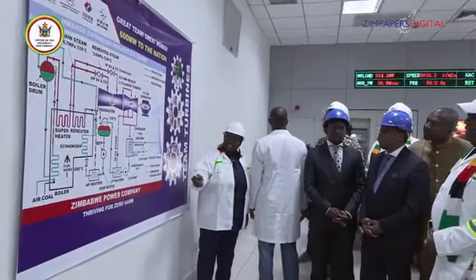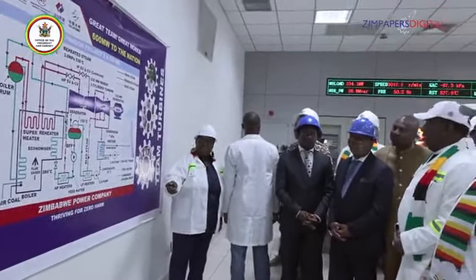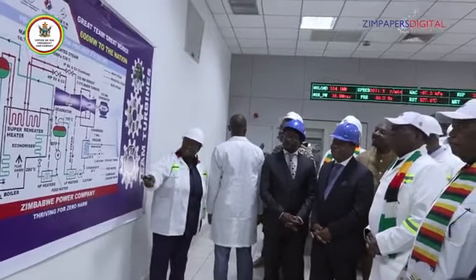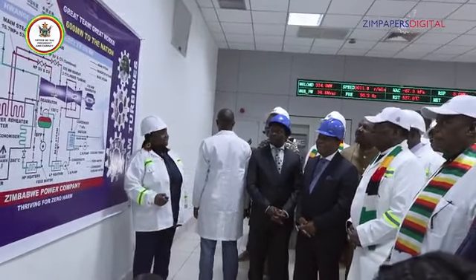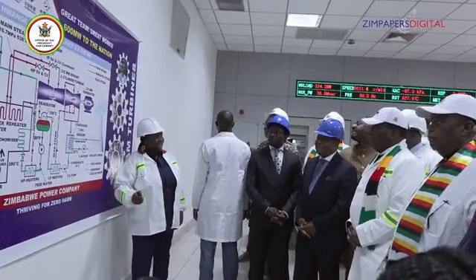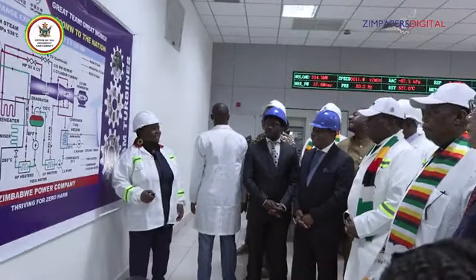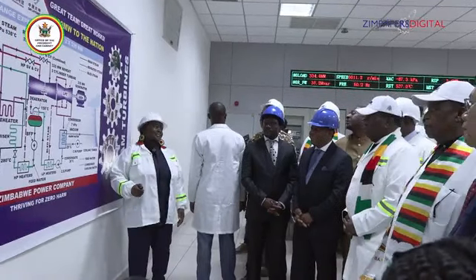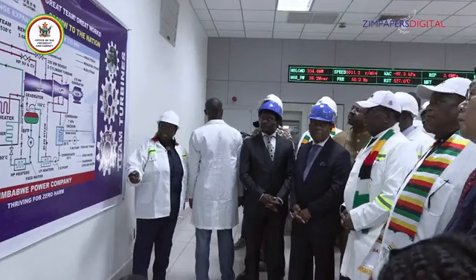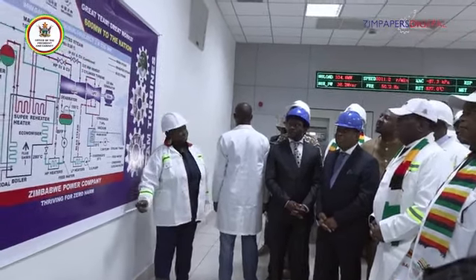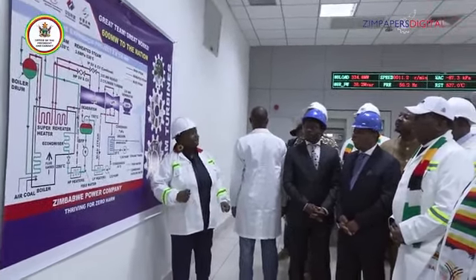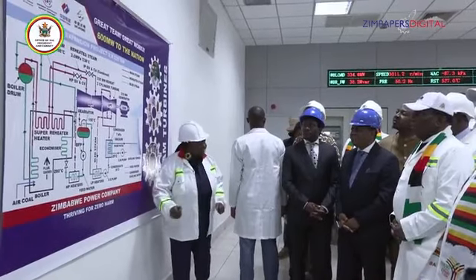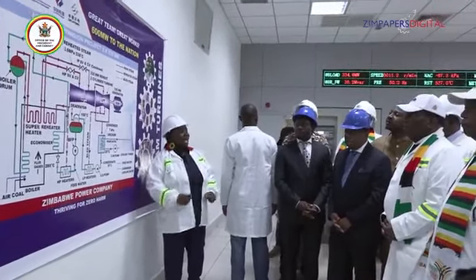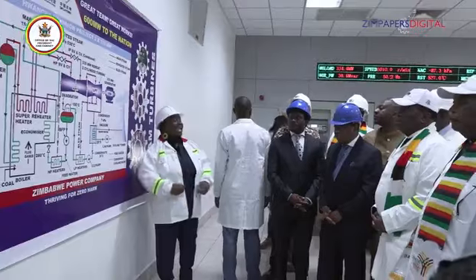It becomes heat energy, and we produce steam, which exits at these parameters: 16.7 MPa pressure, which is 80 times the pressure in your car tires, at 538 degrees, exiting via the pipework. All these pipeworks were subjected to hydrostatic tests at 1.5 times the working pressure, according to world standards and Zimbabwean law.